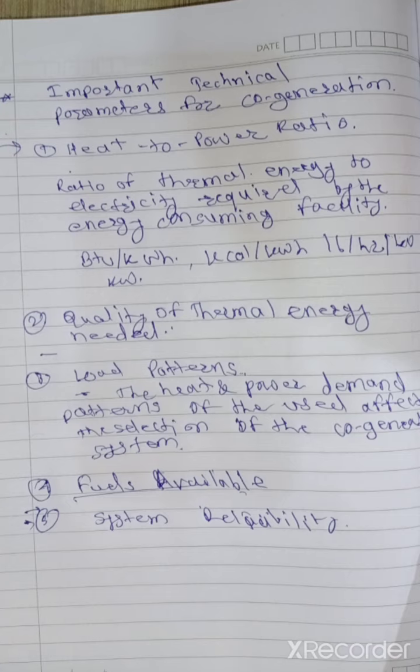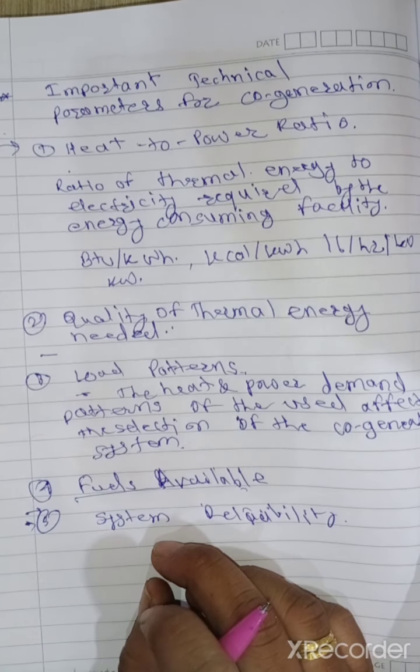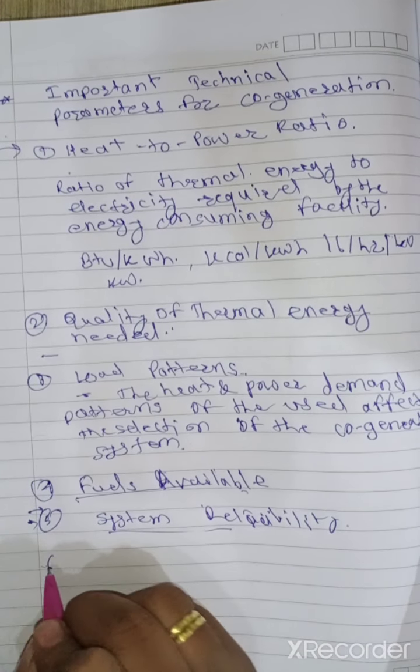For instance, the pulp and paper industry cannot operate with prolonged unavailability of process steam. In such instances, the cogeneration system to be installed must be modular. That is, it should consist of more than one unit, so that shutdown of a specific unit cannot seriously affect the energy supply.